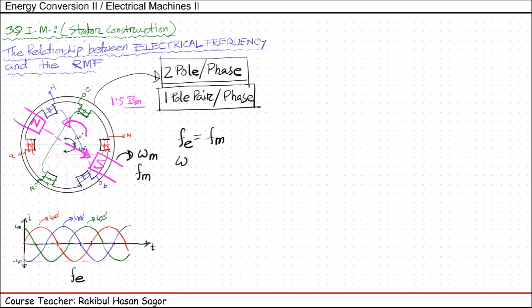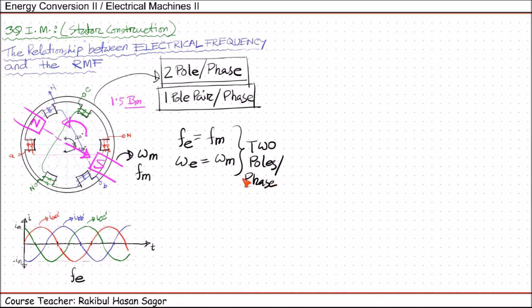Hence we can write: ωe (electrical speed in radians per second) equals ωm (mechanical speed in radians per second), where mechanical speed means the speed of this rotating magnetic field. This is for the two-pole-per-phase case. We will see what happens if we have a higher number of poles per phase later on, but for this configuration we understand that for two poles per phase the speed of the rotating magnetic field is exactly equal to the supply frequency.